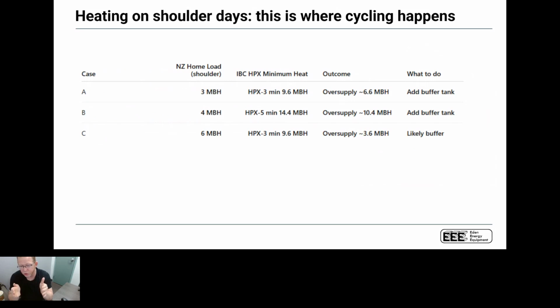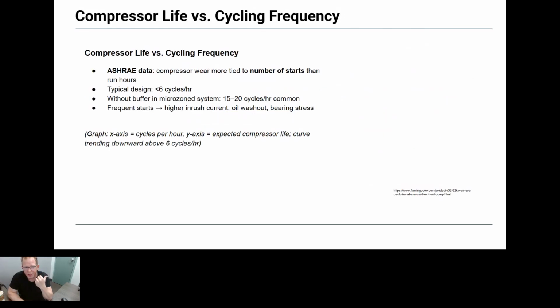We have to make sure that when we look at a buffer tank, we're not looking at a Polaroid picture, right? It's easy to go there in February and go, yep, everything's working great. And then they call you in April and go like, I don't know what's wrong. My unit keeps locking out at high pressure. I can't explain why. And I know why. It's trying to deliver BTUs into the space, but it's trying to do it with a fire truck, right? So you need a garden hose and somebody's pulled up from the fire department and they're literally sandblasting your system with that many BTUs. That's the effect of no buffer tank when it's not at design.